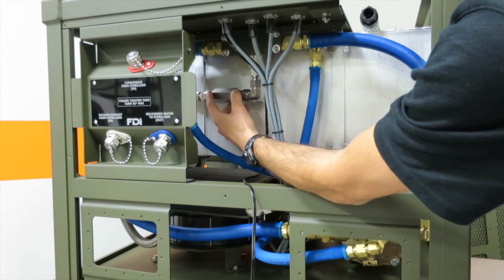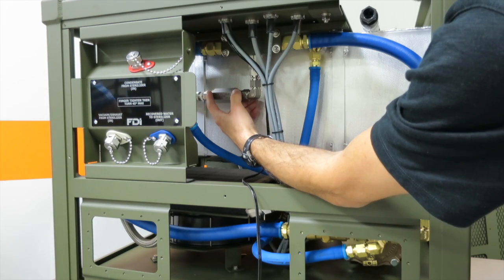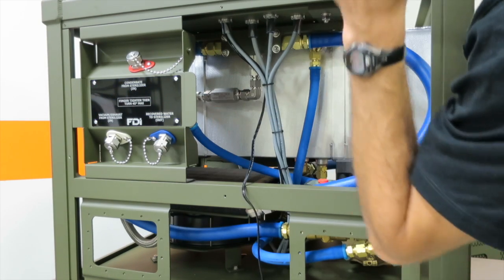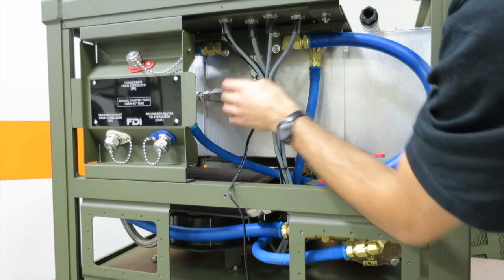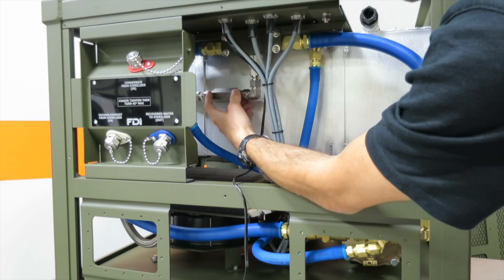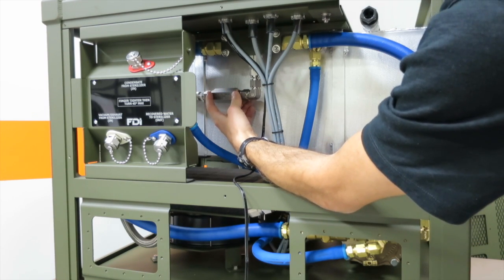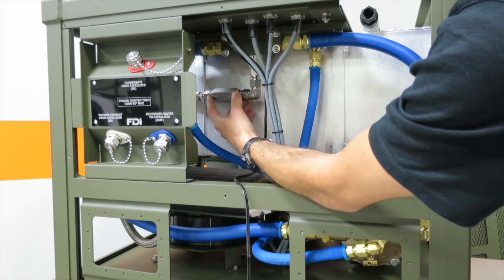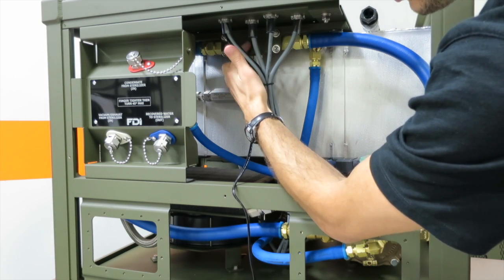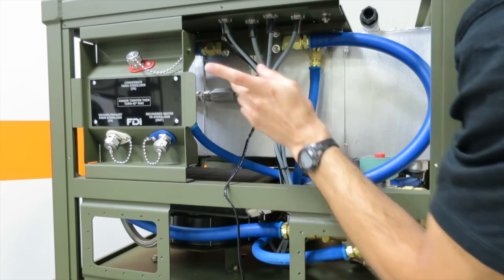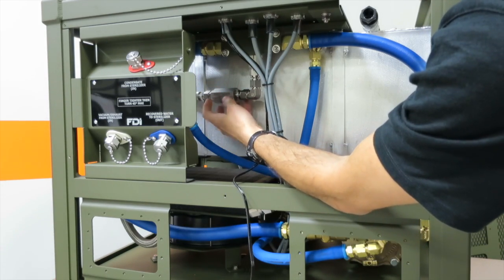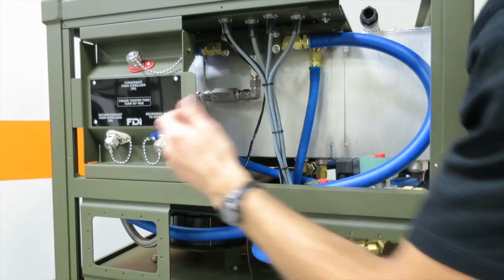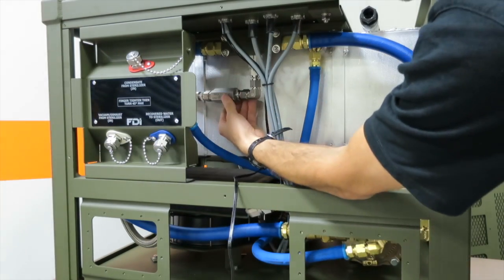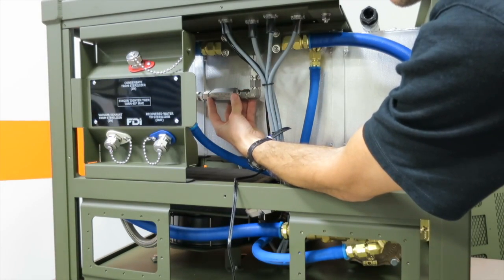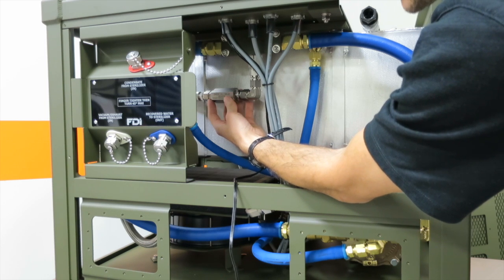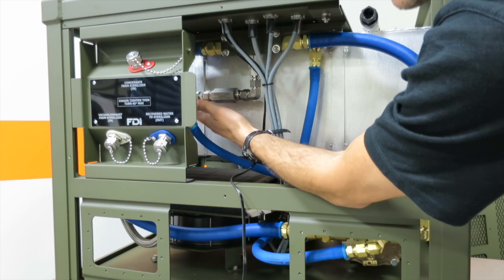This check valve's function is that whenever the chamber is under vacuum, say you're performing a vacuum leak test, or you're in a vacuum pulse on the conditioning phase, you don't want to pull all that water back through into the chamber. So this check valve prevents backflow into the chamber. It's a very important valve for vacuum, and this does hold vacuum on a vacuum leak test.